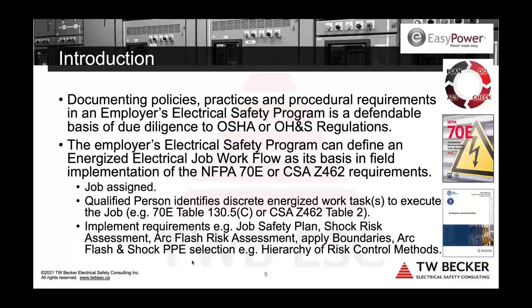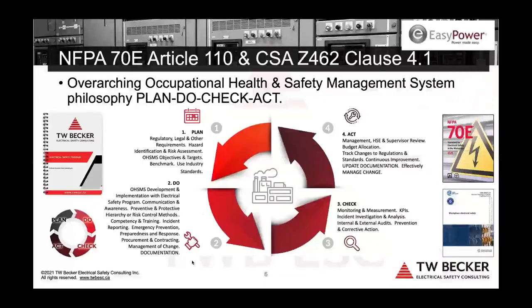In fact, here's the more detailed graphic for that on this slide. All right, so we've got this regulatory oversight for regulations, and ultimately we have to have a plan, and it should really be an occupational health and safety management system with this supporting electrical safety program that 70E and Z462 mandate. Plan, do, check, act, all right? Then we implement that plan, right? This program is developed, it's rolled out, but it needs field documentation. This energized electrical job workflow is a way to communicate that concept ultimately to the worker in the field.